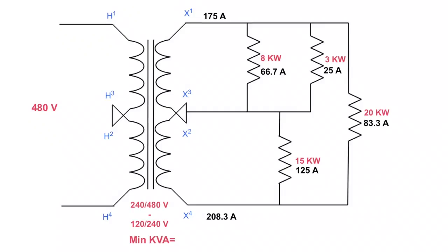While we're at it, let's determine what the neutral current is — it's not really necessary, but it's a good habit to get into. If I have 208.3 amps on one line but 175 amps on the other, that means 208.3 is traveling along and suddenly becomes 175. The difference went along the neutral: 208.3 minus 175 gives you 33.3 amps on the neutral.